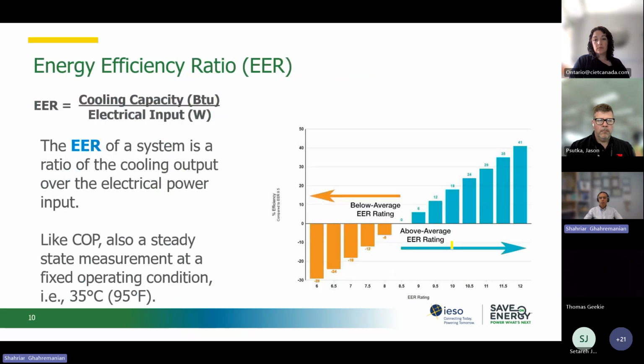The other metric, again in a steady state similar to COP, is the energy efficiency ratio, or EER. These are also shown in the spec sheet of a heat pump by the manufacturer. EER is just looking at the cooling capacity. It means how much cooling is provided at this temperature, 35 degrees Celsius or 95 degrees Fahrenheit, divided by the amount of electricity that is input to the heat pump.